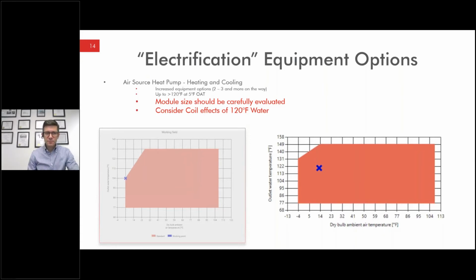The note I'll make is there are two notes in red. The first is, as many of you have probably experienced, the old New York City compressor rule: trying to stay lower than 15 horsepower compressors to avoid the need for an operating engineer on site full time. It's a big deal in New York, and depending on the scale or type of building you are designing, it could be a deal breaker if you're not meeting that 15 horsepower limit. So I would caution you to be careful as you're designing and selecting modules and the conditions you're operating at. Warmer water might shift you into a larger horsepower compressor. We've found that 120 for this 15 horsepower module is somewhere in the sweet spot, as we've been trying to design around 120 as the supply water temperature. You can get warmer water, and for a building that doesn't have a concern about an operating engineer, there are options to push that up. But keep module size in mind as you're doing selections.